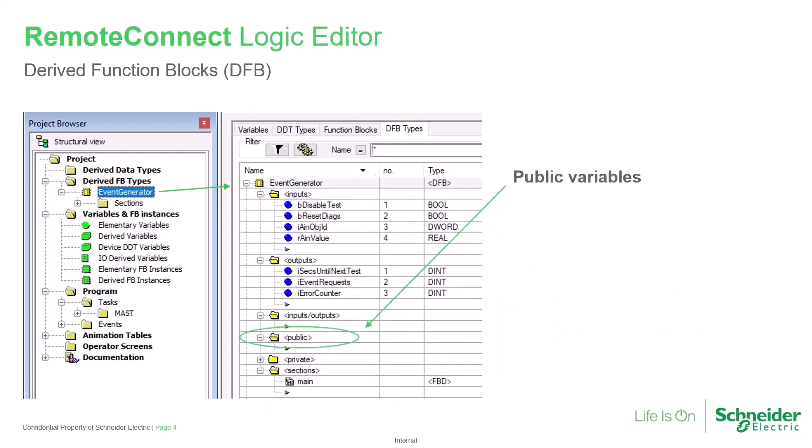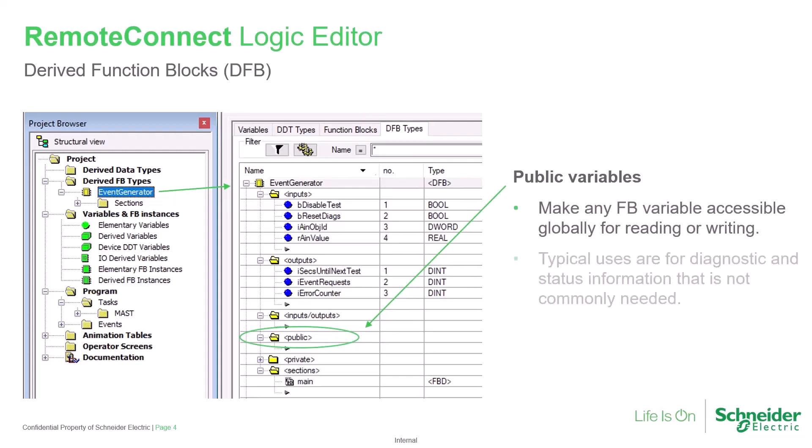A DFB may also include public variables. These will be available globally anywhere within the entire application. A common use for a public variable is to share diagnostic or status information with the rest of the application. For example, a motor starts counter.